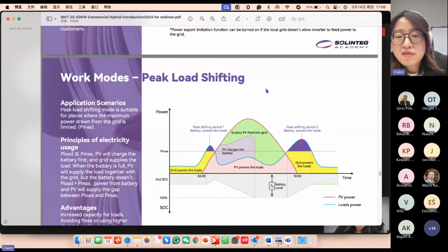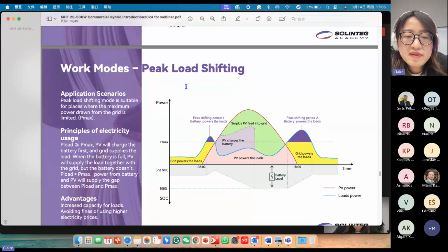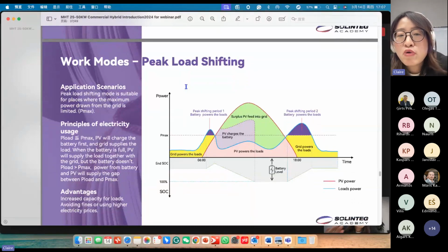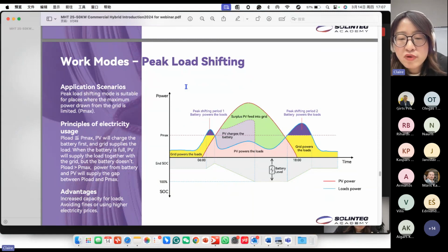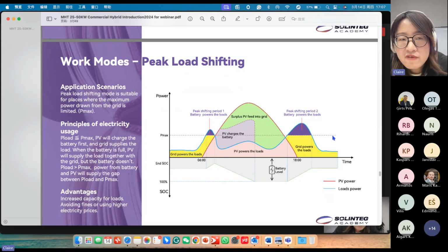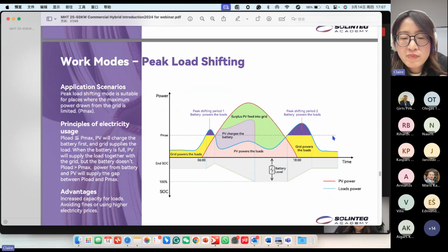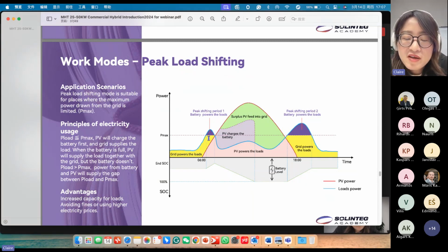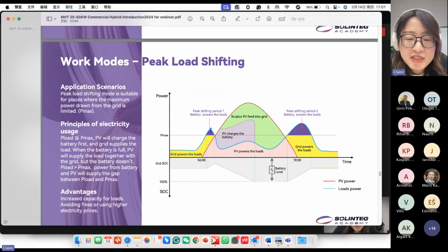And for the peak load shifting function, which can also be called the peak shaving function, this is quite useful in some countries. They request the customer to sign a limited contract with the grid company for the maximum power they can take in from the grid. For example, if we sign a contract with the grid company for a maximum of 10 kilowatts from the grid, and this time we have a 15 kilowatt load, if we take 15 from the grid, we may be punished, or maybe the extra power will be charged at a high price rate. So we can use the power from the battery to fill the gap of this 5 kilowatts.